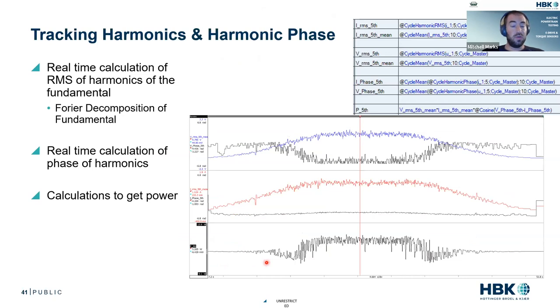In addition to flux, we can do harmonic tracking and understanding of harmonics. So we can look at what is your fifth harmonic current? What is your fifth harmonic voltage? What is the phasing between our fifth harmonic voltage and current? And ultimately, what is the power of our fifth harmonic? So we can actually look at what is my harmonic voltage? What is my harmonic current? And what is my harmonic power? We can start to understand the losses of different individual contributing components. I think this is really powerful for understanding a machine and understanding machine control to analyze your losses, to understand where my loss is coming from. And again, we have our equations in the top right and a screenshot from our software in the bottom.